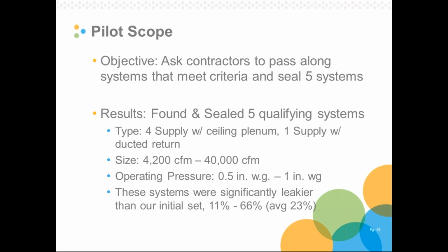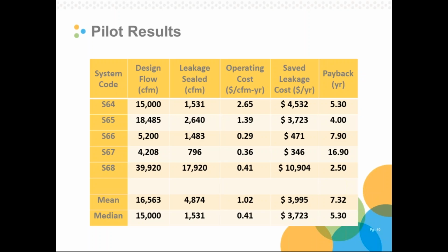These systems were significantly leakier than our initial set, and maybe this shouldn't be surprising. I've mentioned a few times now that leakage depends on flow and pressure, and once we start filtering through these things, we find much better results. So these systems leaked on average 23%, ranging from 11 to 66%. So here are those results. We sealed between 800 and 18,000 CFM on these systems, and we saved between about $350 and $11,000 a year. Payback averaged about 7 years and varied between 2.5 years and 17 years.